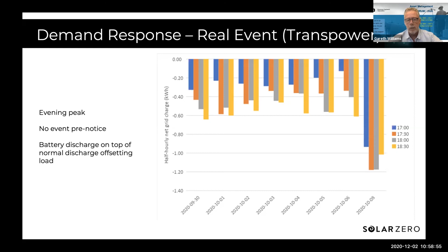So this is an event that we ran with Transpower, a real one in Hamilton, and you can see the bars up until the event show typically what the batteries were doing, and then on the event, we can see we were able to increase what the battery was doing based on its normal operation. This was during a normal evening peak period without any pre-notification, so it was showing how much we could respond just by overriding what the batteries were normally told to do.